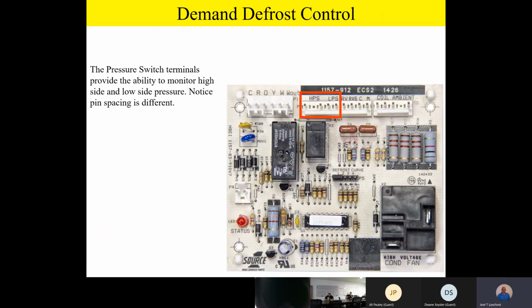Okay, good. So let's go ahead and start taking a tour of the board and the sensors and the pressure switches and so on. You'll notice on the top of the board, as we take a look at our photo, we have an HPS and an LPS. That's our pressure switch terminals. Those are inputs and outputs to the pressure switches. If you look closely at the photo, you'll see that the pin spacing is different between the high pressure switch and the low pressure switch. The reason they do that is so you can't mess them up. If you try to plug the high pressure switch onto the low pressure switch, it's not going to work. So that pin spacing is different, and that's our input and output from the board for our pressure switch terminals.